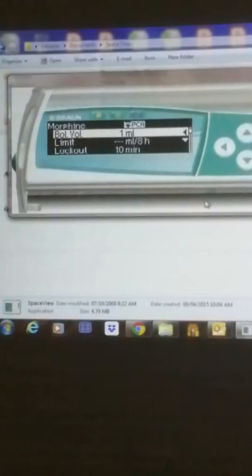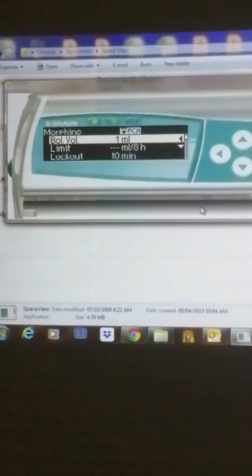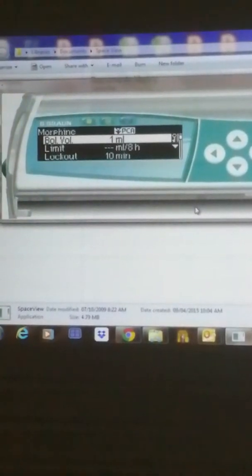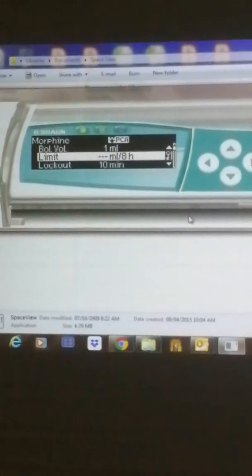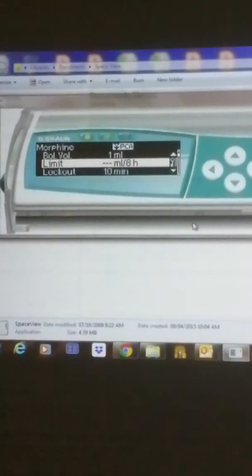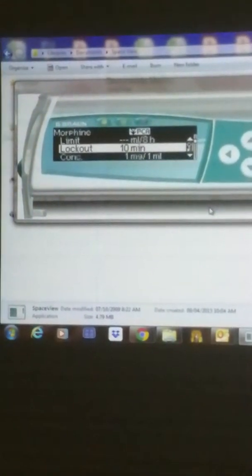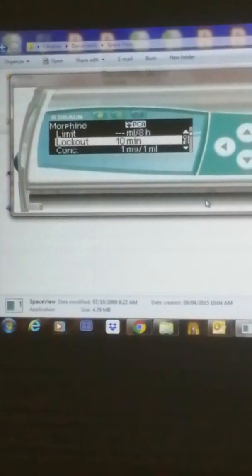The bolus volume is how many milliliters the patient receives per button press. Then the limit — the total limit over 8 hours. And then the lockout time — the time between each press where the patient is allowed to receive a dose. The patient can press as many times as they want, but if the lockout is 10 minutes, they will receive one dose now and the next active one only after 10 minutes. Between those presses, nothing is delivered.